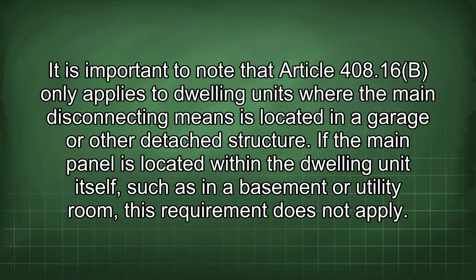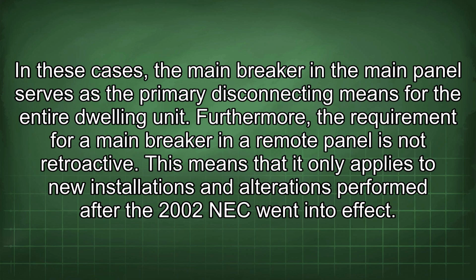It is important to note that Article 408.16b only applies to dwelling units where the main disconnecting means is located in a garage or other detached structure. If the main panel is located within the dwelling unit itself, such as in a basement or utility room, this requirement does not apply. In these cases, the main breaker in the main panel serves as the primary disconnecting means for the entire dwelling unit.